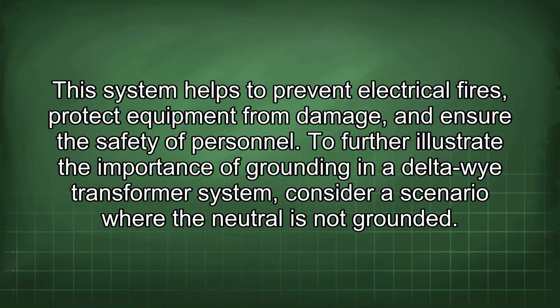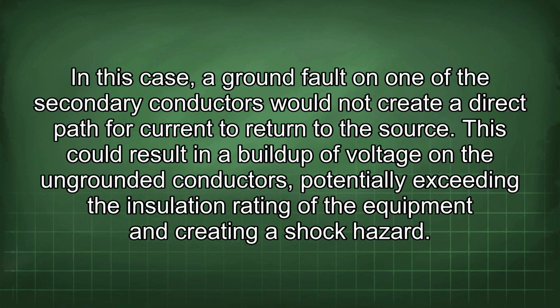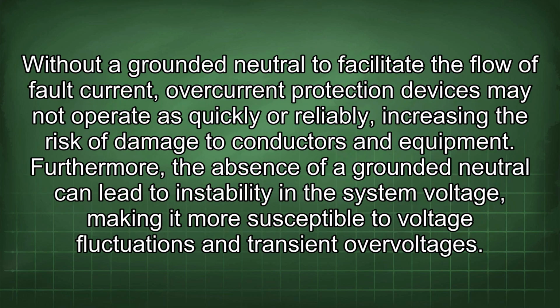To further illustrate the importance of grounding in a Delta-Wye transformer system, consider a scenario where the neutral is not grounded. In this case, a ground fault on one of the secondary conductors would not create a direct path for current to return to the source. This could result in a buildup of voltage on the ungrounded conductors, potentially exceeding the insulation rating of the equipment and creating a shock hazard. Without a grounded neutral to facilitate the flow of fault current, overcurrent protection devices may not operate as quickly or reliably, increasing the risk of damage to conductors and equipment.